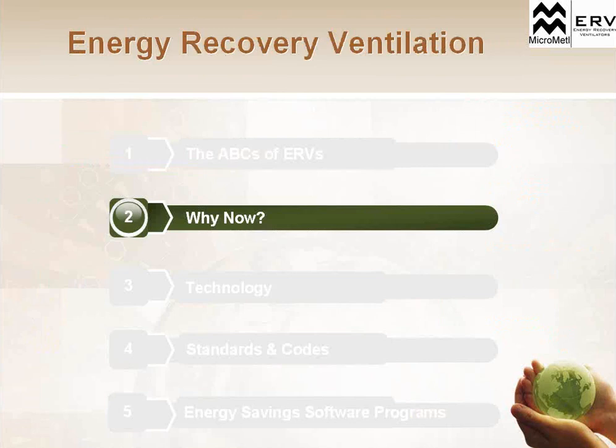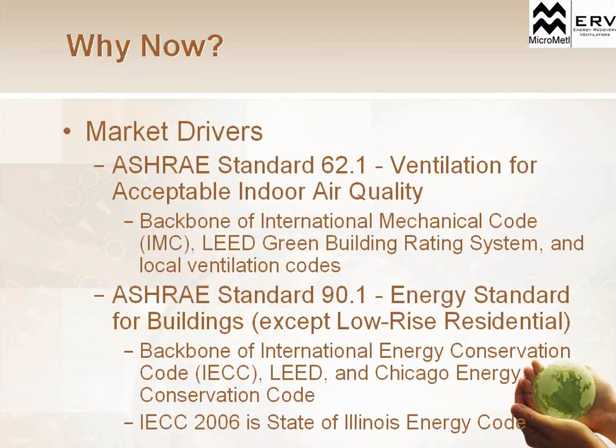So why now? Why is it in the last 3 or 4 years we've been seeing more and more requirements for energy recovery ventilators in codes and standards, and why has ERV become a new buzzword in the last 5 to 10 years? Some of the market drivers specifically are the ASHRAE standards. ASHRAE standard 62.1, which was first instituted in 2004, outlined the ventilation for acceptable indoor air quality. So this set a level of ventilation that was required for indoor air quality in each different type of space, like in a school or in a restaurant. It dictated how much ventilation needed to be brought in. So that's our ventilation standard that we're looking at.